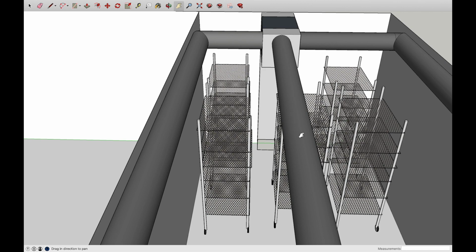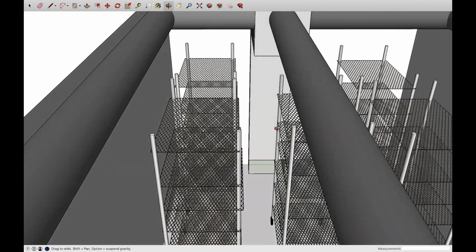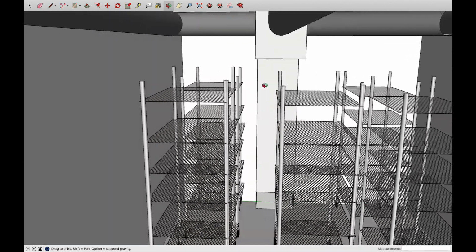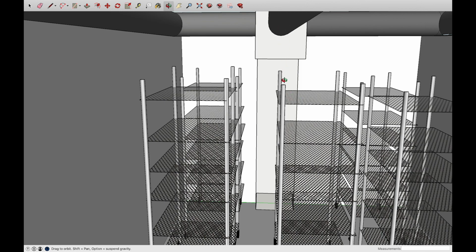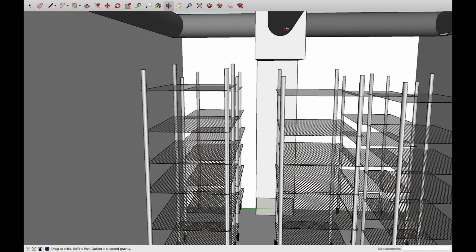It's fabric as well, but instead of our traditional laser cut holes, these are a lot more micro in size. So they're a micro mesh hole. What it is going to allow us to do is move the air, the volume, the CFM, but it's not going to do it at a high velocity. So it's literally just going to slowly rain down in this center portion. And so between the sides and the center, we have good, even coverage.